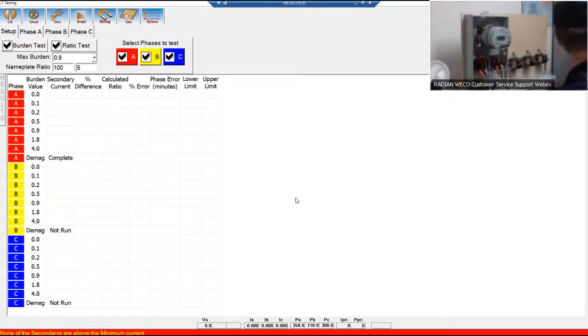I'll go ahead, we're going to put 20 amps into the primary. So I should see 1 amp on my secondary. And now if you look at the bottom of my software screen here, on IA, IB, and IC, we have 1 amp across the board. So the RW is correctly reading my A phase voltage for a reference voltage, as well as A, B, and C phase secondary current. Now at this point, with it reading above the 1/8 minimum secondary current, I can start my test.